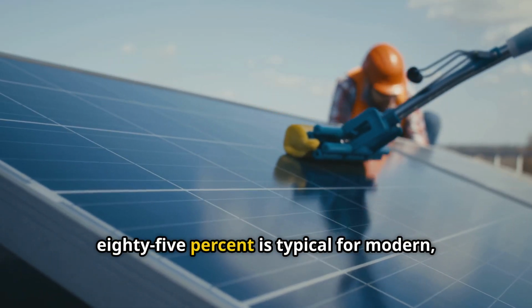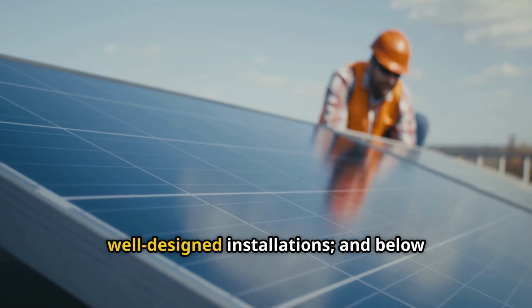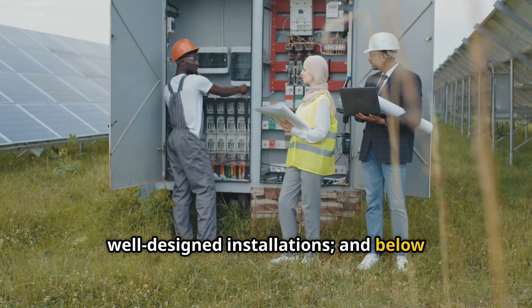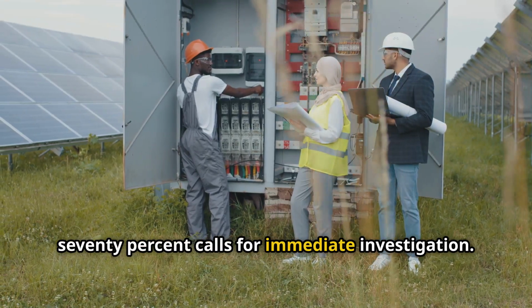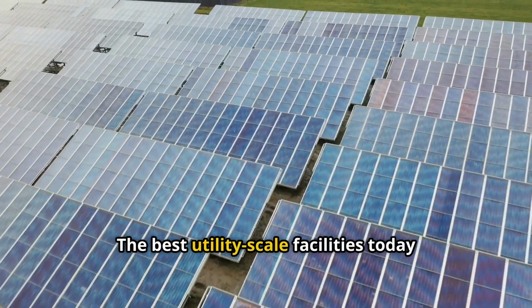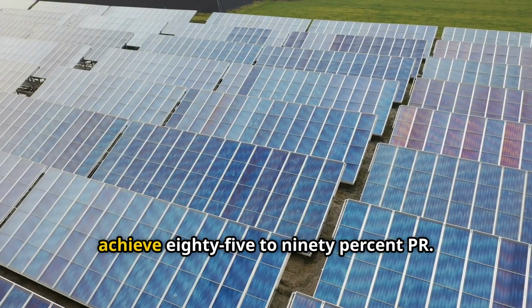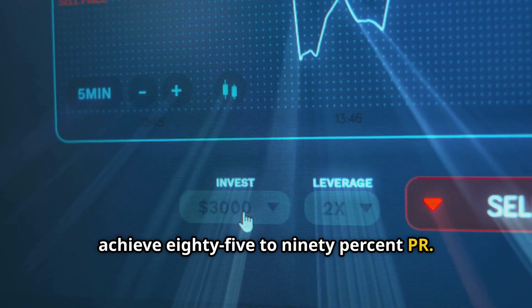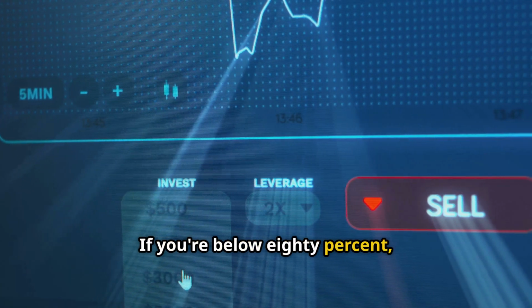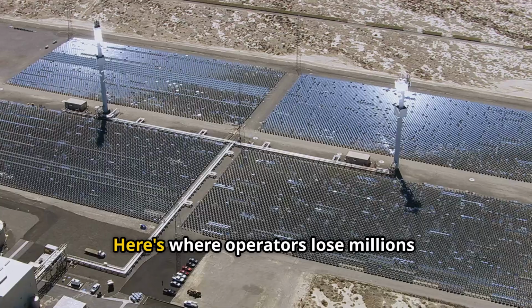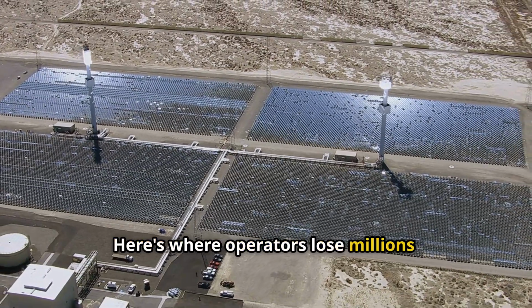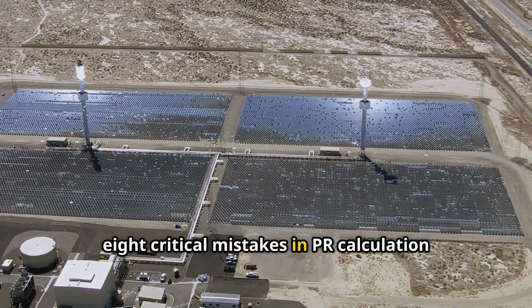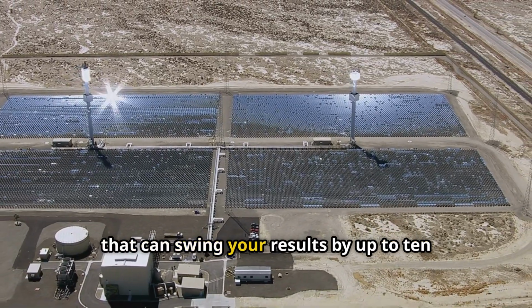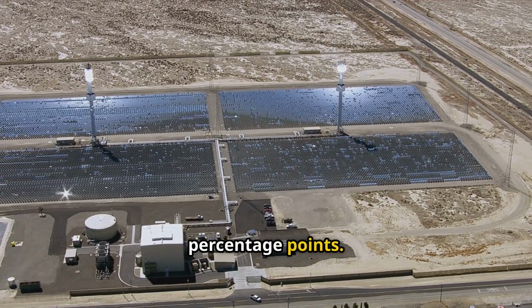80 to 85% is typical for modern, well-designed installations. And below 70% calls for immediate investigation. The best utility-scale facilities today achieve 85 to 90% PR. If you're below 80%, you're leaving money on the table. Here's where operators lose millions. 8 critical mistakes in PR calculation that can swing your results by up to 10 percentage points.